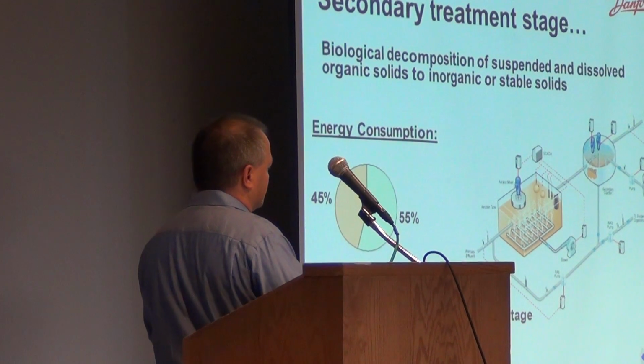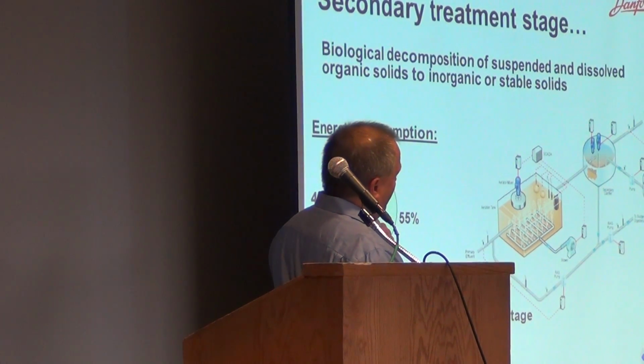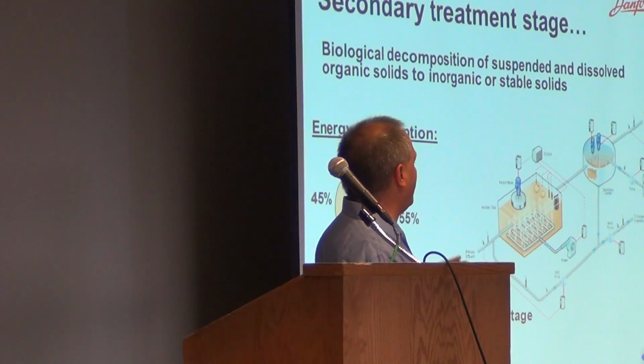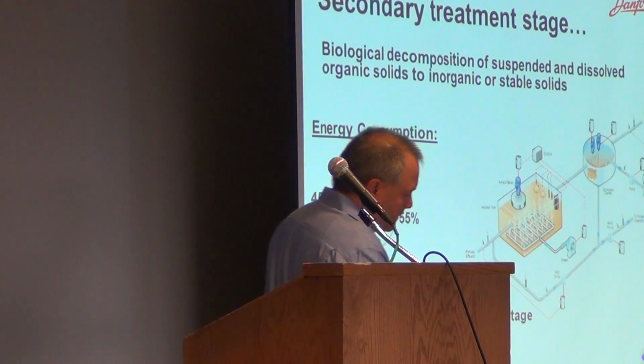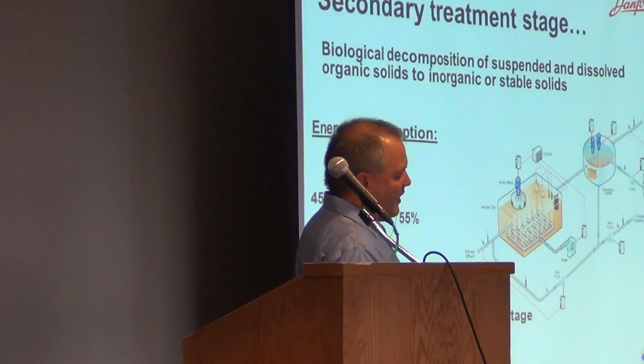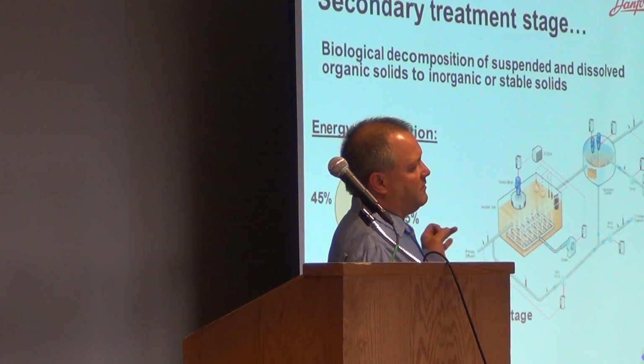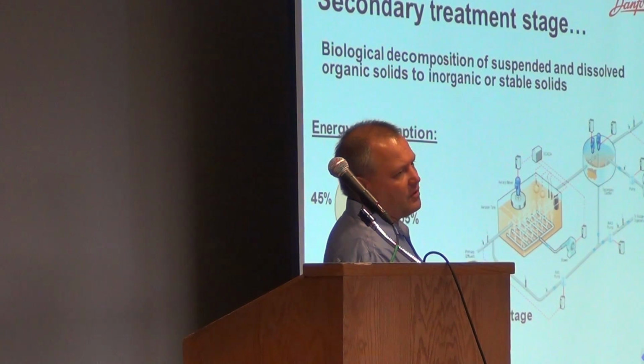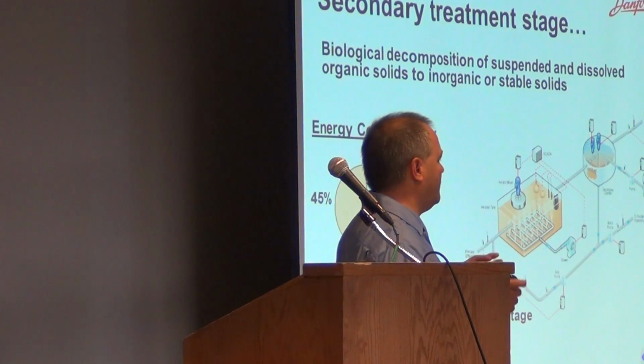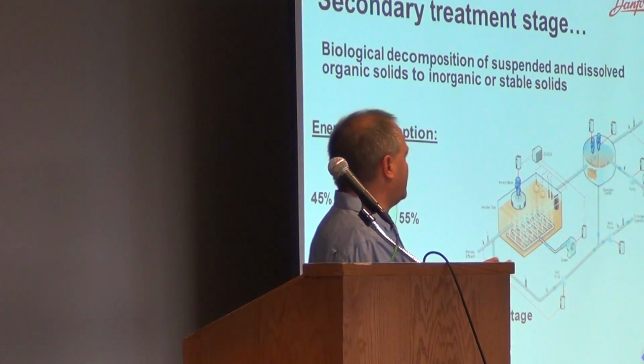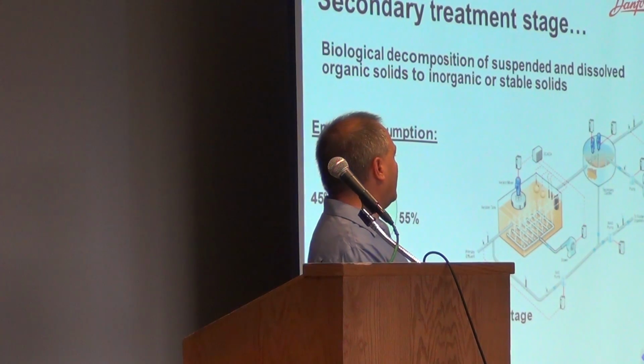Secondary treatment stage. This is where we really get into the aeration and stuff. Part of the issues of putting a drive on a blower, everybody's come to me and told me at the show even, is that they can't get the weights to lift it. They have to run it up so hard before the blower actually lifts the weights, and we actually get aeration going up the pond. A lot of drives have to have a secondary or 2-speed jumper put in order to make the drive operate that way. Our drive automatically, we can program it and tell it that we need a boost right away, and then we level up from there.